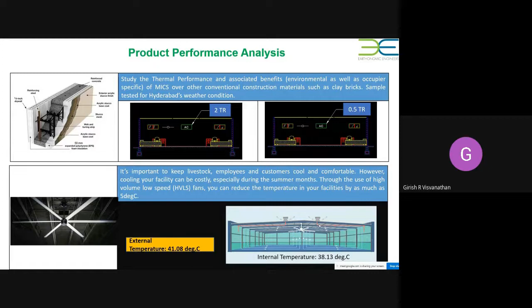Going forward, and being quick here, what are the other technologies? Not just materials, selection of lighting systems or polycarbonates on your wall can ensure free daylighting across your system. This is a building in Gujarat, an automobile factory, where we removed the skylights and made them into wall lights so there's no heat gain, only light coming in from the sides. This facility gets about 300 lux of free lighting from 9 a.m. to 5 p.m. every day. If you're wondering why this space isn't getting lighting, it's basically a paint shop where they want to view the facility in showroom conditions, not in sunlight conditions.